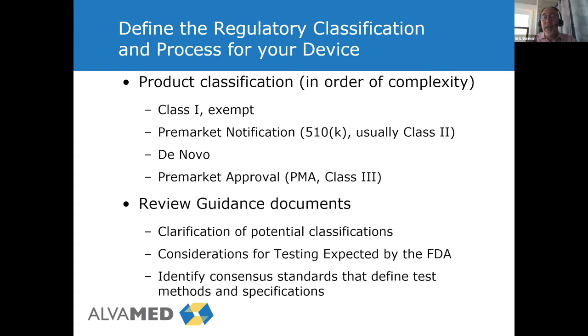I'm going to say in the United States, 90%, 95% of the products that make it to market here are in the pre-market notification process. De novo is a process where you don't quite fit in the pre-market notification process, the 510K process. The 510K process is one of substantial equivalence clearance - you're showing that your product is the same as a product that's already out there, already marketed. You're showing that through testing and your intended use, your indication for use, that you're the same as what's currently out there.